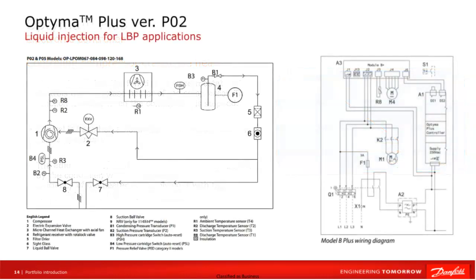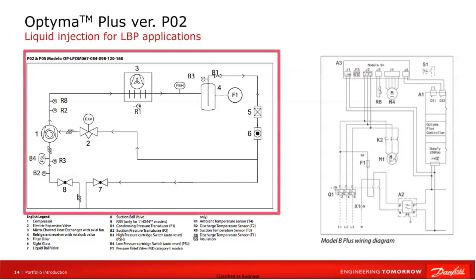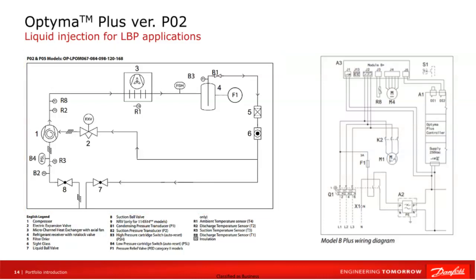In this slide, we will focus on possibilities offered by Optyma Plus unit in the P02 version. The left side shows the installation diagram of the unit, showing various elements of the fittings, regulation and security system. The P02 version of the unit is equipped with the electronic expansion valve that enables precise liquid injection into the compressor, which helps to reduce the discharge temperature.